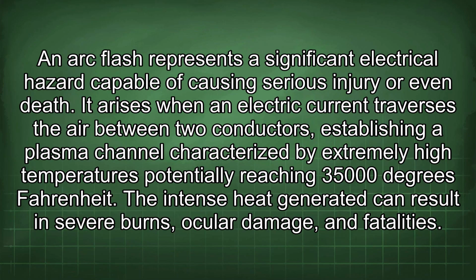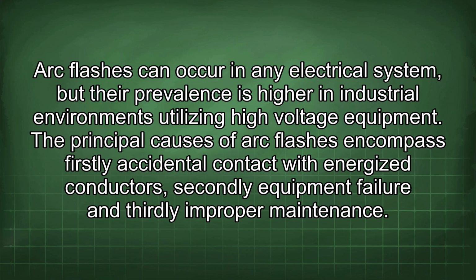An arc flash represents a significant electrical hazard capable of causing serious injury or even death. It arises when an electric current traverses the air between two conductors, establishing a plasma channel characterized by extremely high temperatures potentially reaching 35,000 degrees Fahrenheit. The intense heat generated can result in severe burns, ocular damage, and fatalities. Arc flashes can occur in any electrical system, but their prevalence is higher in industrial environments utilizing high voltage equipment.